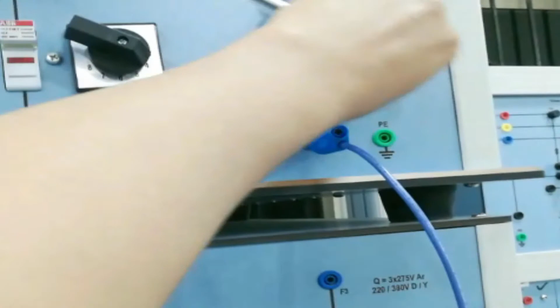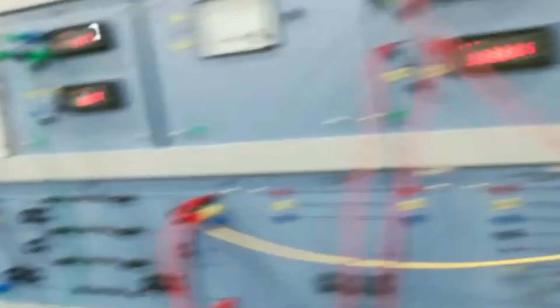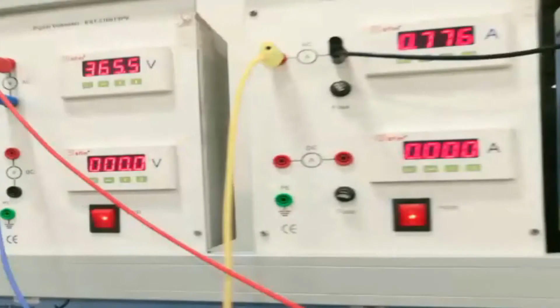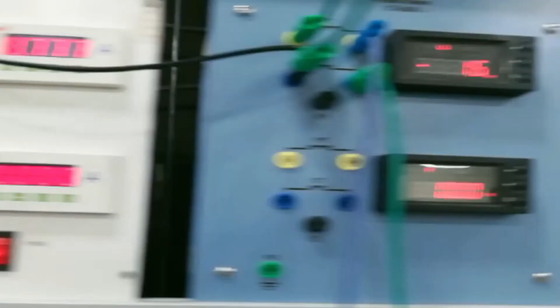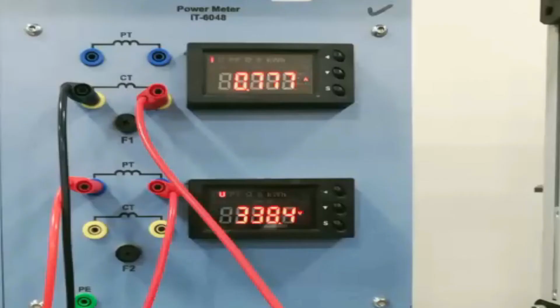Now again changing the load to the R4 value. You can see now the sending end voltage is 365.5 and current is 0.77 ampere, whereas the reactive power has decreased to 1.4. This value is very small, almost negligible reactive power at R4 load, and real power is 164.7. Receiving end current is 0.77 ampere and the voltage is 338.